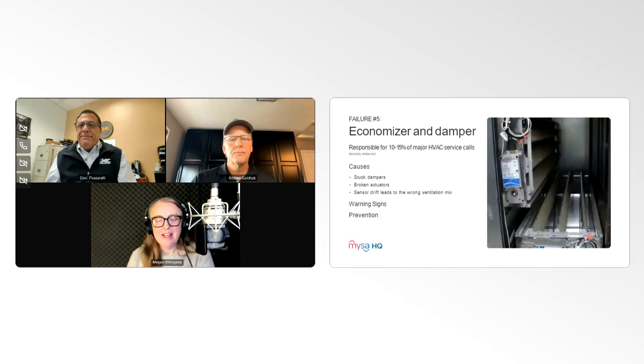Excellent. Thank you so much. Andrew, how can FMs maintain an economizer and maximize its useful life? Sure. So definitely annual economizer function testing, making certain, for example, is the enthalpy controller working correctly? So really taking advantage of the free cooling when it's available. The economizer and all the sensors do operate in a harsh environment. So making certain that outdoor and indoor air sensors are calibrated, that they are feeding the correct information back to the enthalpy controller, and of course, things should be documented as well as part of that preventative maintenance report.